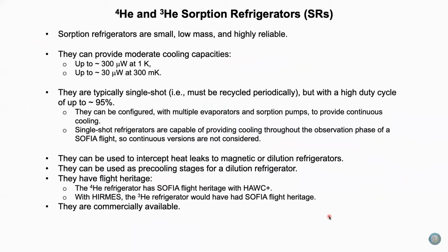Sorption refrigerators. Now these are very useful little things. They're small, they're low mass, and they're highly reliable. There are no moving parts in them. And they can provide moderate cooling capacities up to 300 microwatts at 1 Kelvin using helium-4, and up to about 30 microwatts at 300 millikelvin. That would be using helium-3. They're typically single shot. They must be recycled periodically, but they have a high duty cycle of up to 95%.